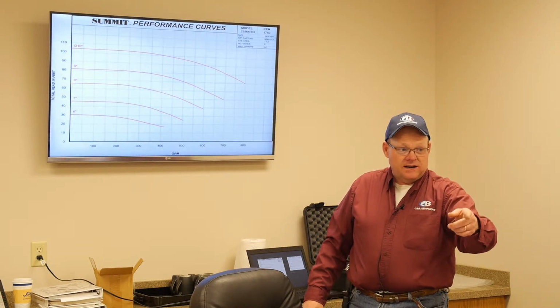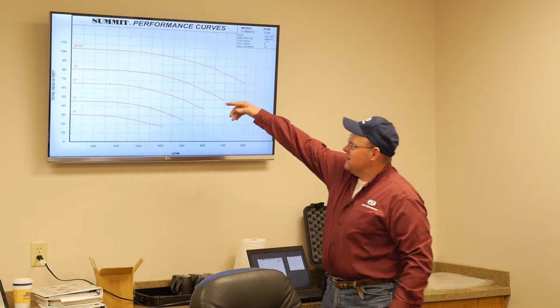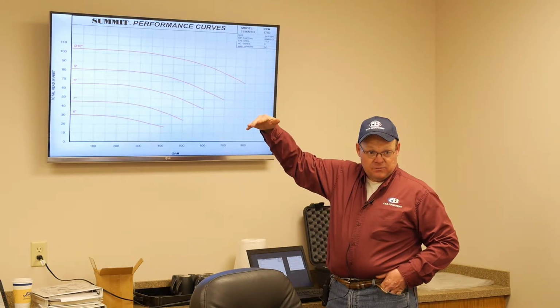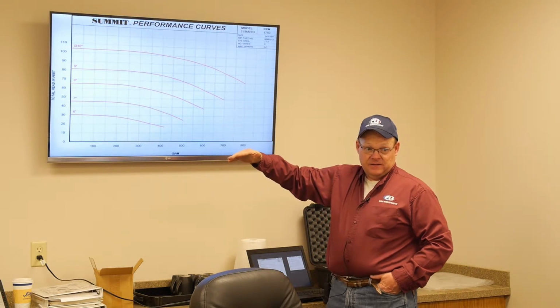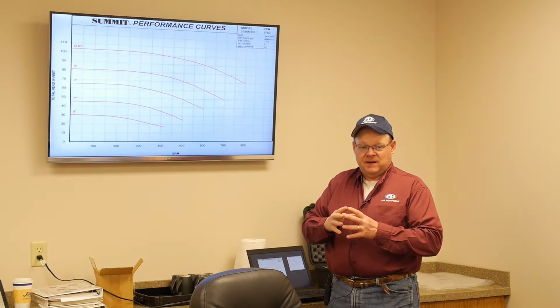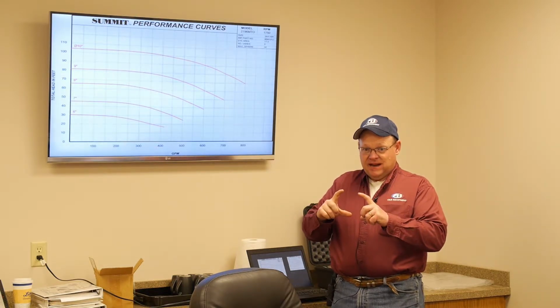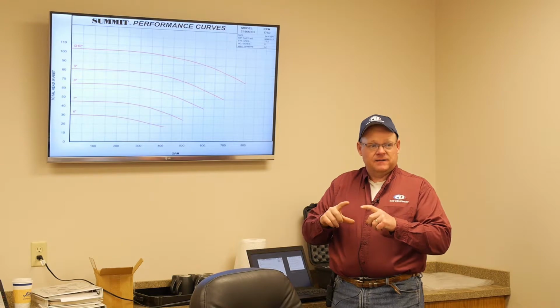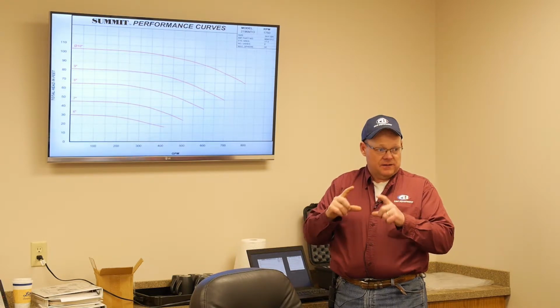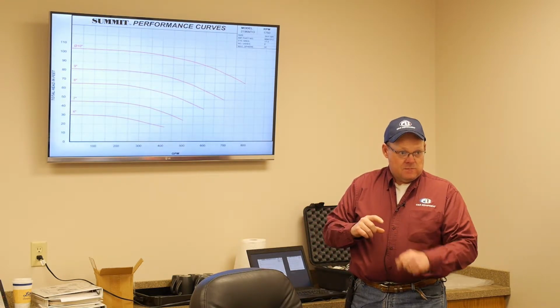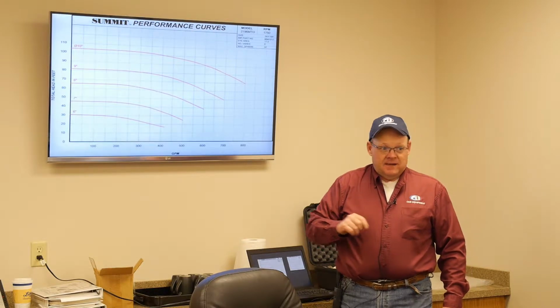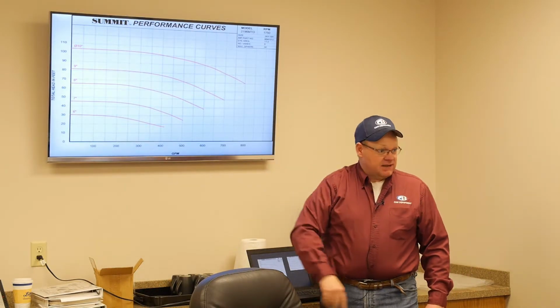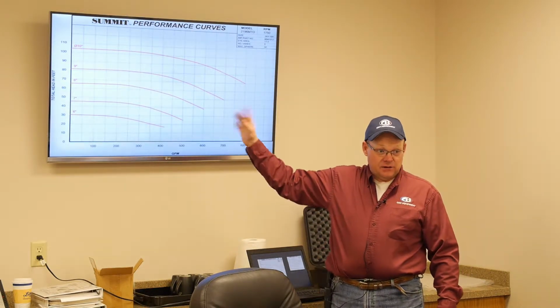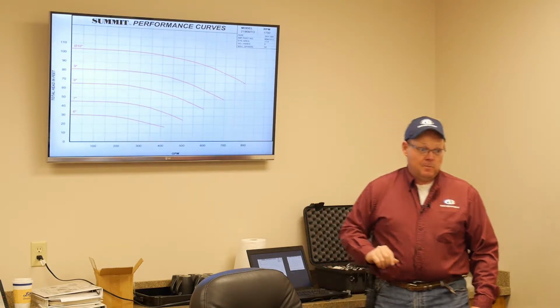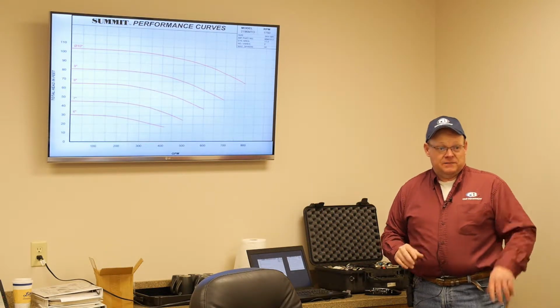If we trimmed it 1 inch, see how that cut our head, our ability for pressure, how it decreased it. Again, it goes back to the same principle. A specific diameter at a specific speed will produce a specific amount of pressure. You would have to change casings though? That's the same casing. That curve represents the same casing. All we did was trim the impeller.